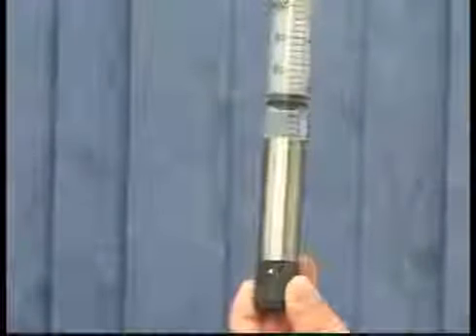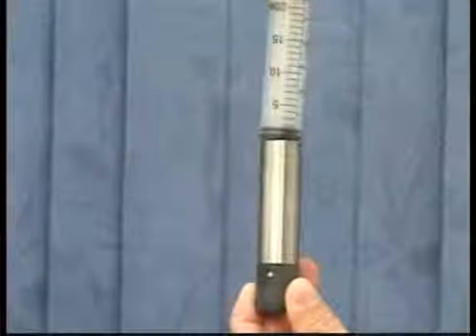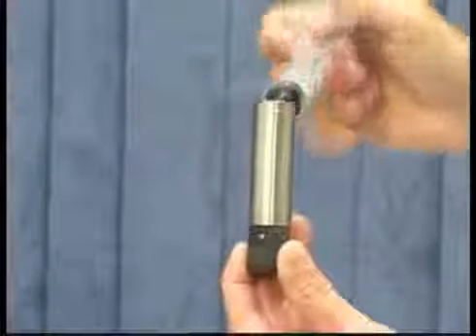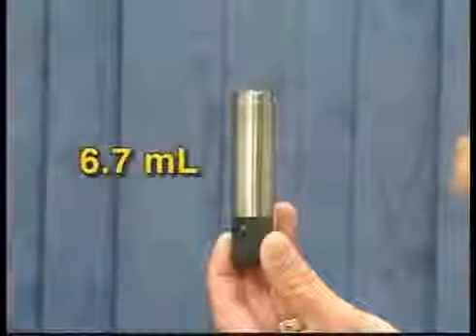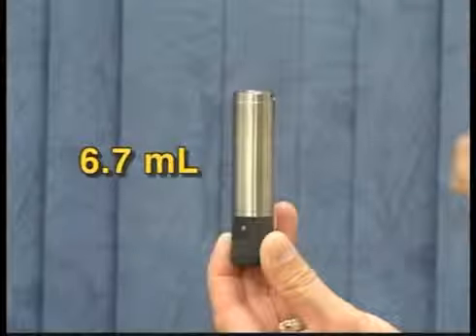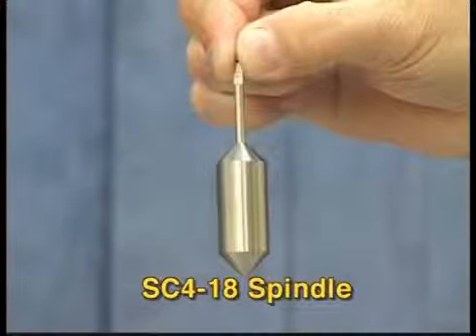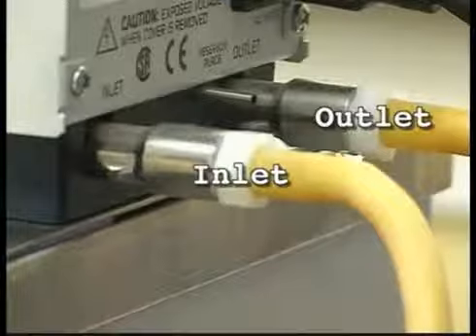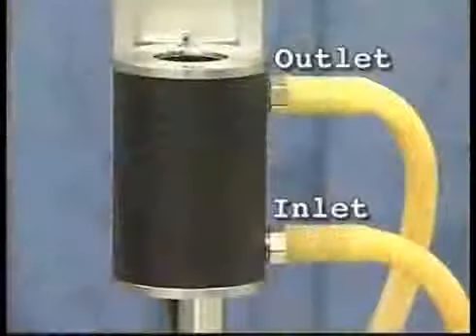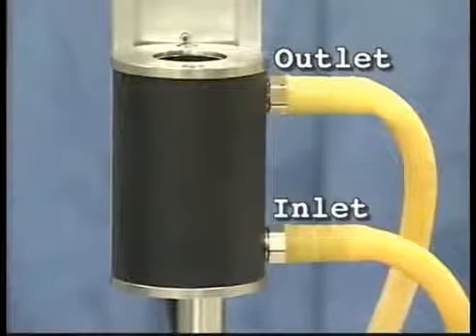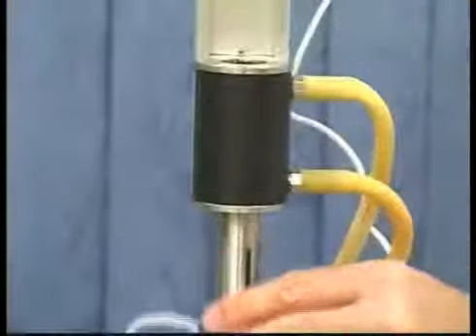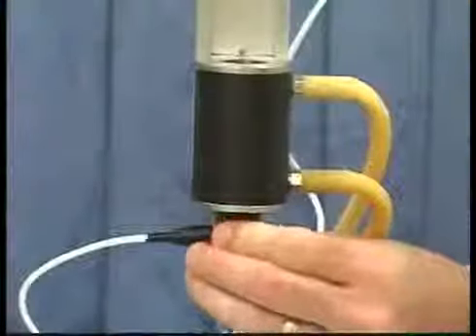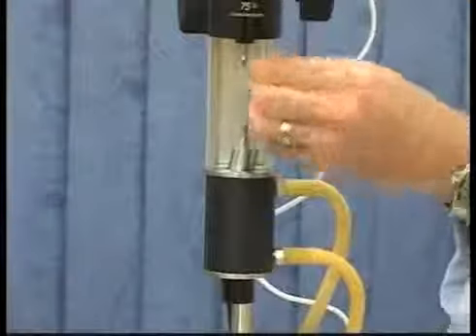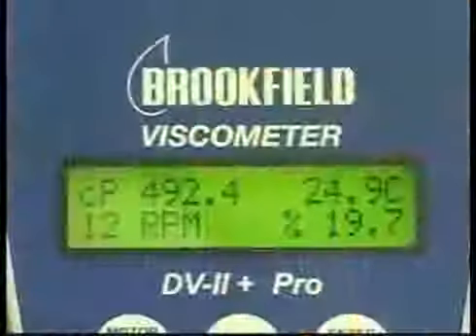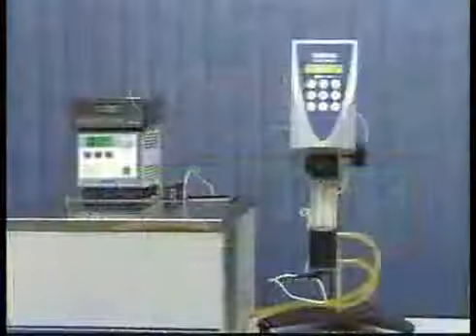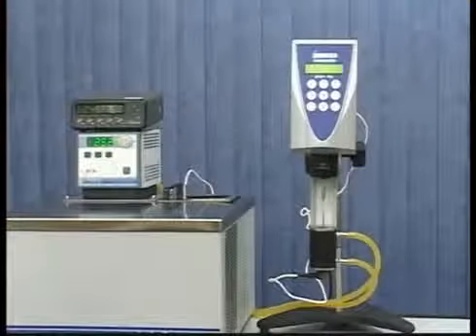Fill the chamber with the correct amount of viscosity standard fluid. In this example, the small sample adapter is using 6.7 milliliters of fluid with a number 18 spindle. Hoses from the water bath inlet and outlet will connect to the water jacket inlet and outlet for proper circulation. For proper temperature equilibration, the fluid and spindle all need to be equilibrated at 25 degrees Celsius. The viscosity standards are very sensitive to temperature.